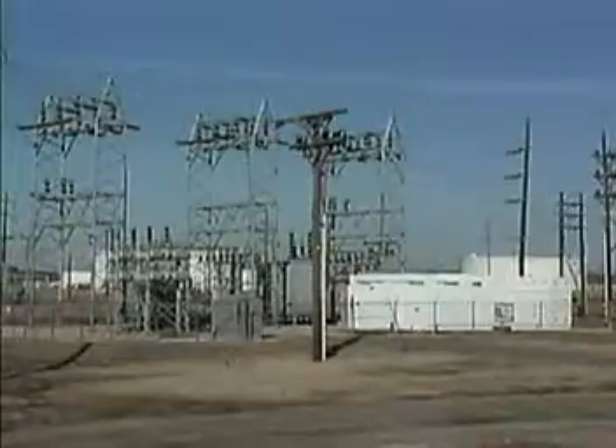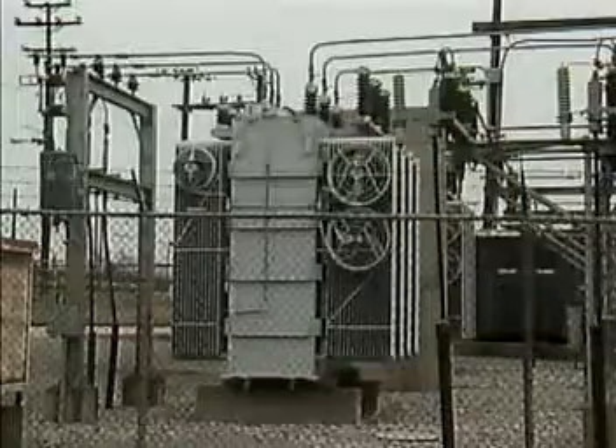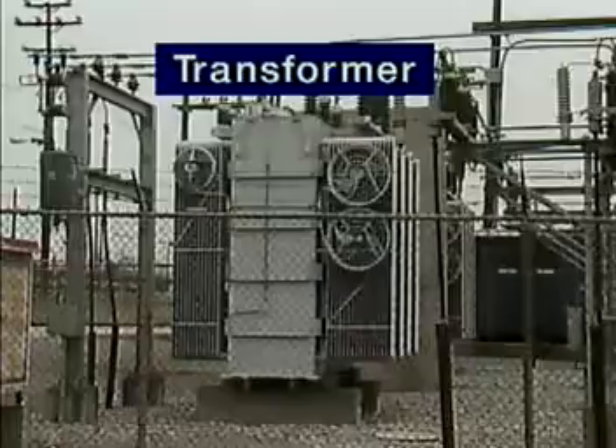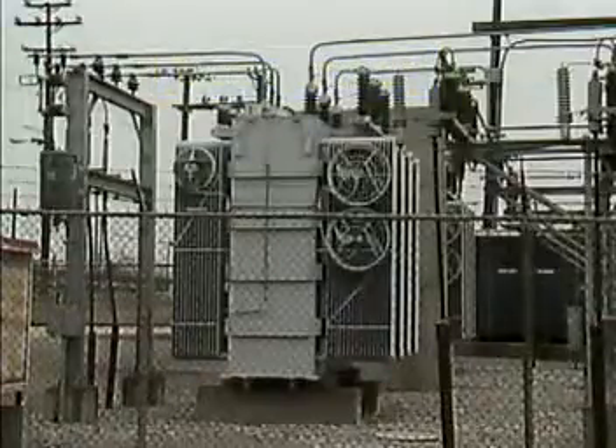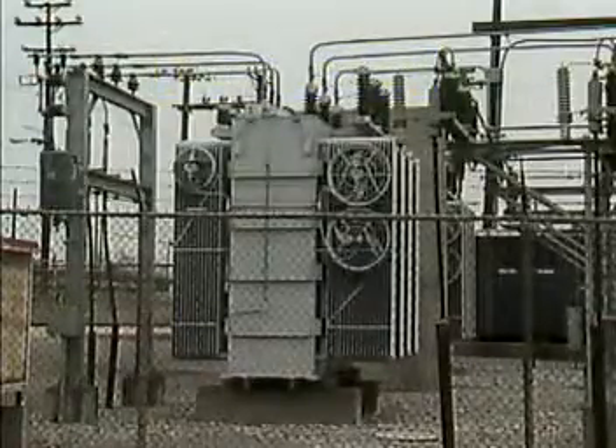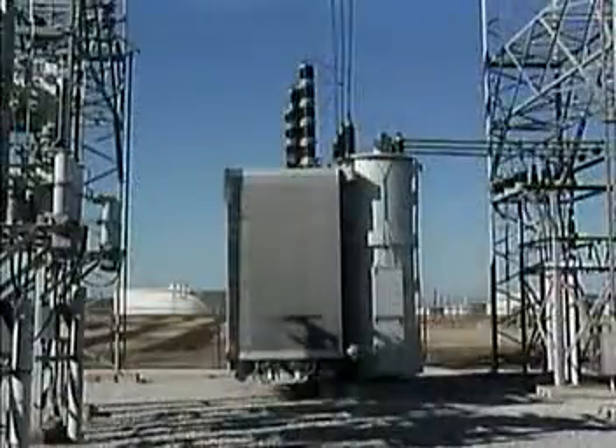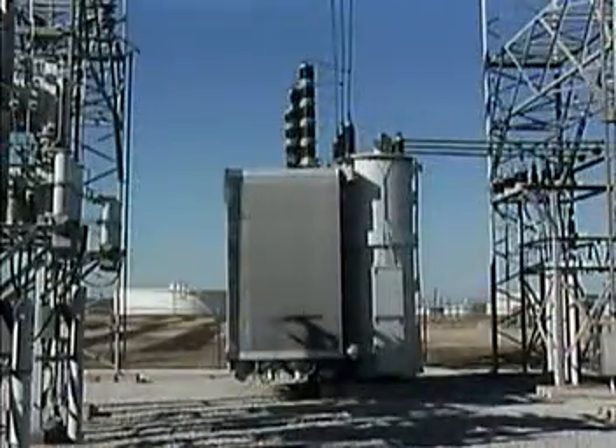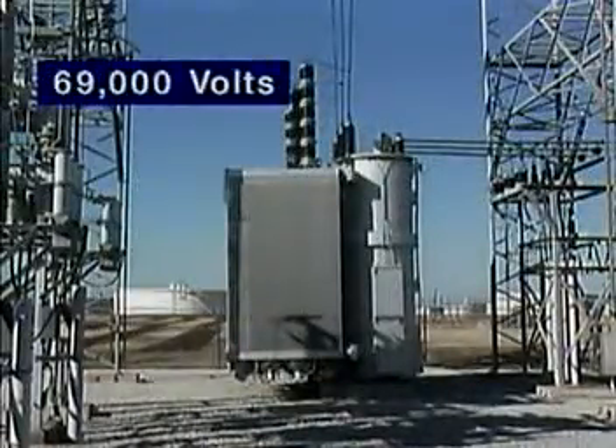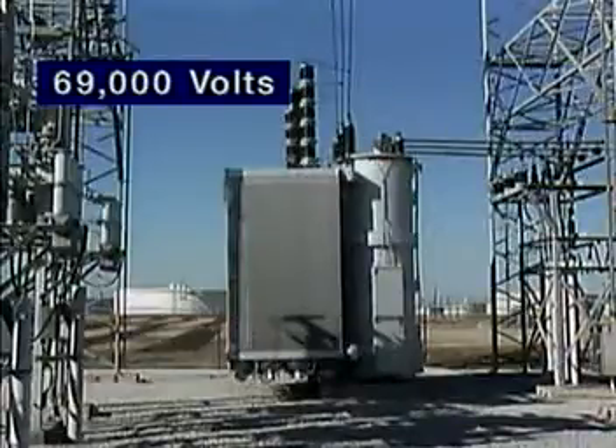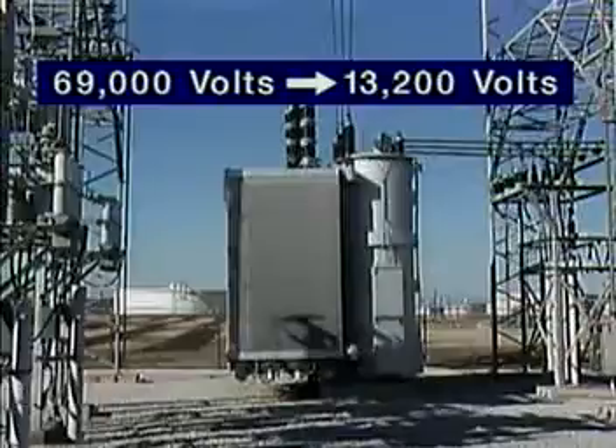Voltage can be changed from one value to another using a device called a transformer. A transformer increases or decreases voltage for various uses. At this plant, the main substation transformer takes the incoming voltage, 69,000 volts, and reduces it to a level the plant can use, which in this case is 13,200 volts.